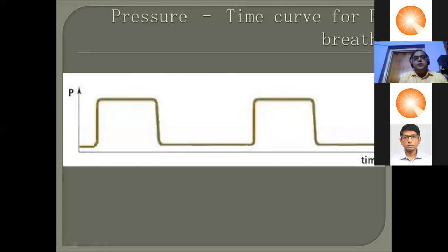So this is what is happening. As you can see, as my inspiration has started, my pressure has gone up to this level. So this is my PIP. It continued for this duration. So this is my TI. As the TI ends, my pressure drops to this level. So this is my PEEP, and it continues at that level for this time. So this duration is my TE, and then the next breath starts, and so on and so forth. This is how a pressure time scalar looks in PC breaths, and we call this pattern a square window pattern. Now remember, this never actually happens in reality, because no machine can bring the pressure instantaneously from this level to that level. All machines have a response time, so this happens over some period of time. So this usually looks a bit like this rather than straight like this. Okay, next slide, please.